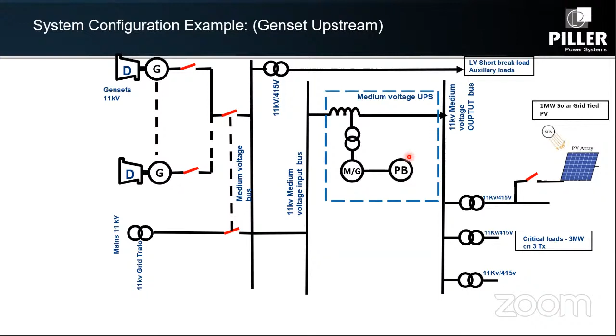This is an example where we have it downstream; you could also have photovoltaic and other renewables connected upstream. The behavior of the UPS is in our control, and we're able to do it bidirectionally. At nighttime, in this example, you could have the full 3 megawatts coming in from the grid supply. There are various ways to do it. This is just an example, because we're short on time, to show you the possibilities, and you should be looking at all these angles too.